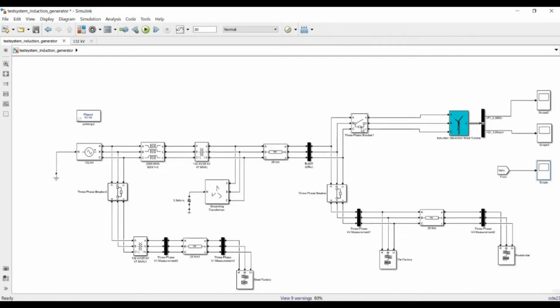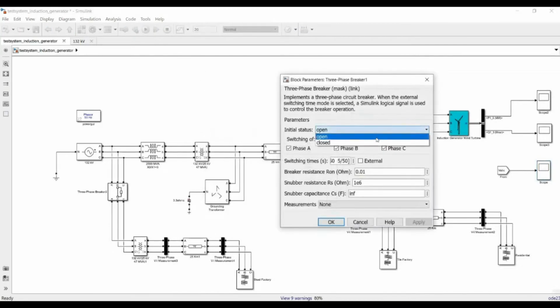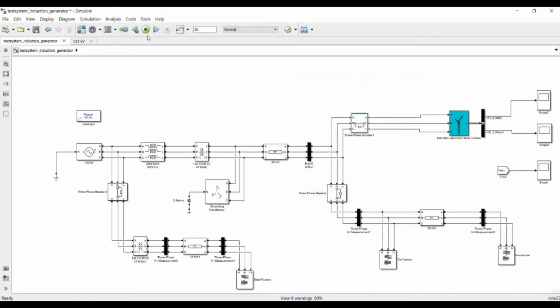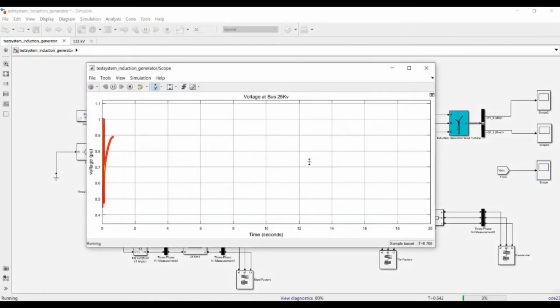Then I will connect the system with the wind turbine. As we can see here, there is a transient response before the voltage goes to a stable state. And after connecting this wind turbine, the system has about 0.97 per unit voltage, which increased from 0.94, but there is a transient response here.